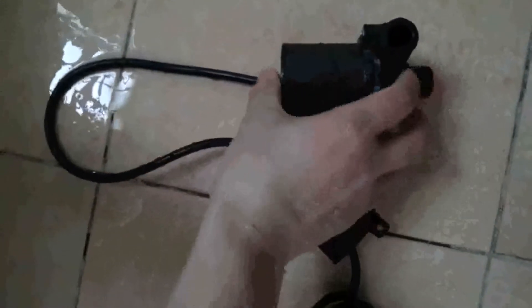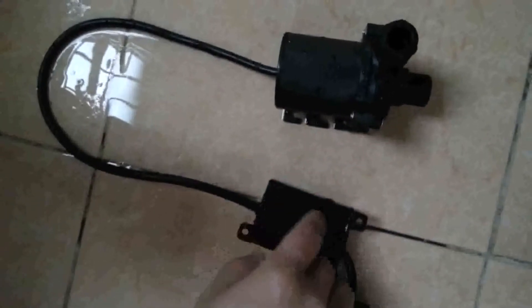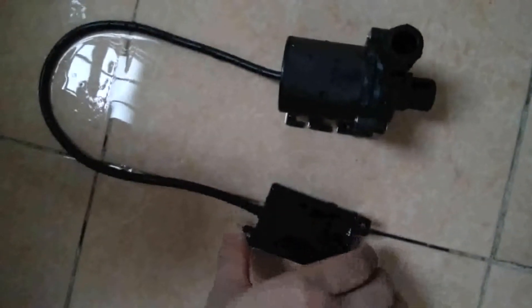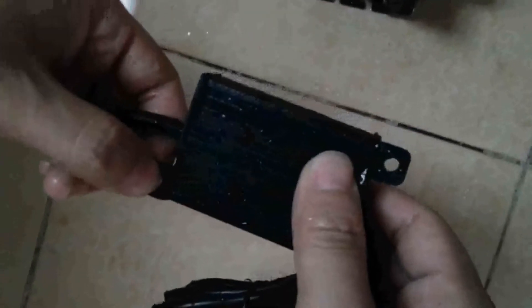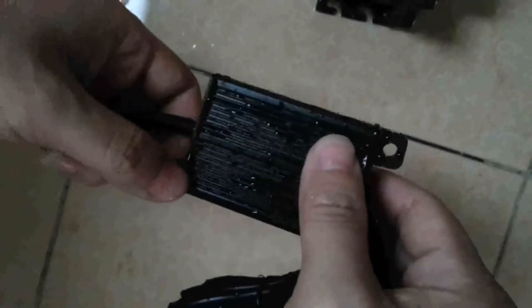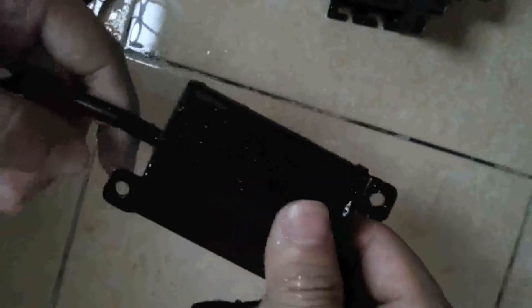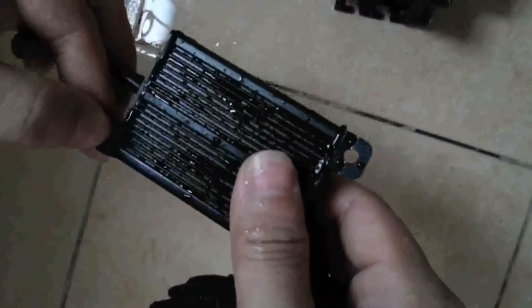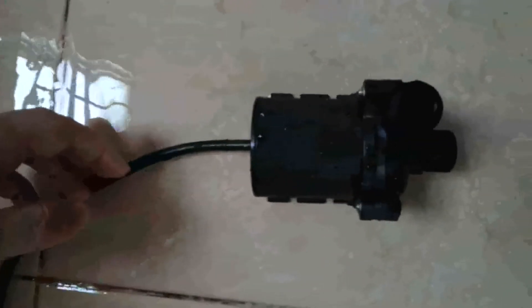This pump's distinctive characteristic is the separation of the pump body and the control circuit box. This box is our pump's brain — it contains all control and protective circuits inside it. This is completely waterproof. However, for stability and reliability, electronic components in higher temperatures could be affected, so if the temperature is over 75 degrees Celsius, this control box should be separated from the higher temperature circulation.